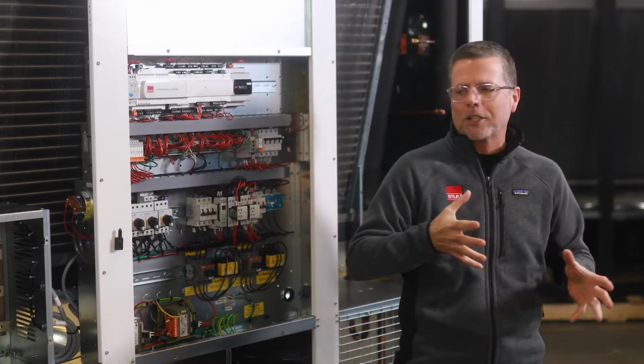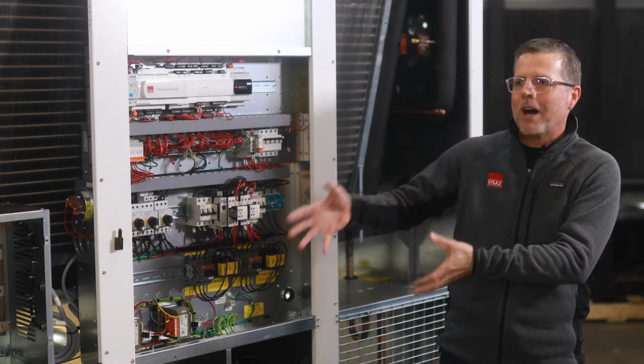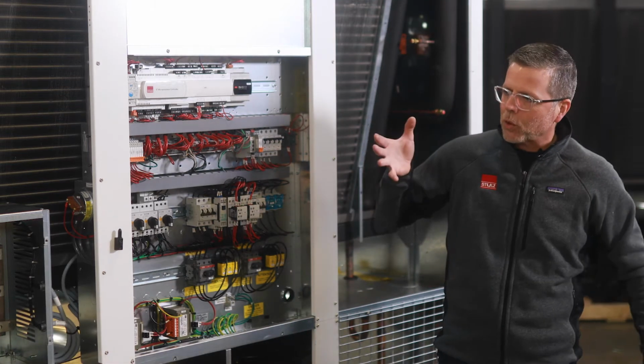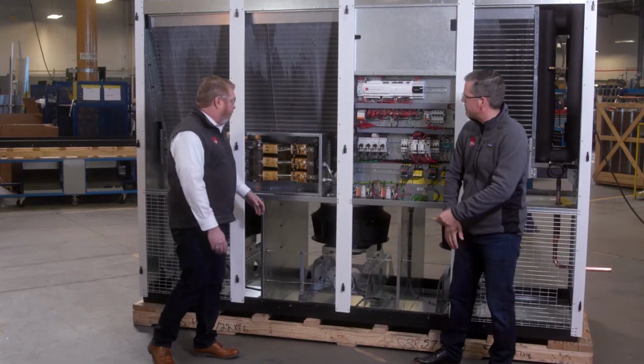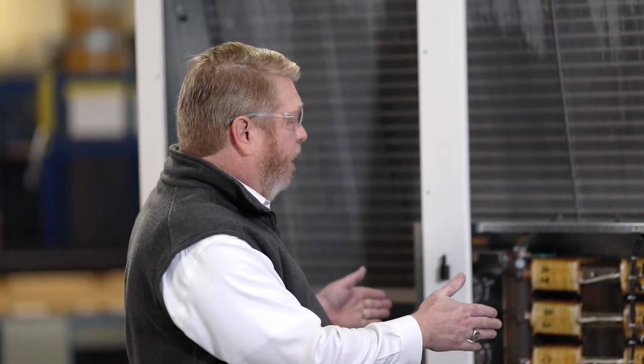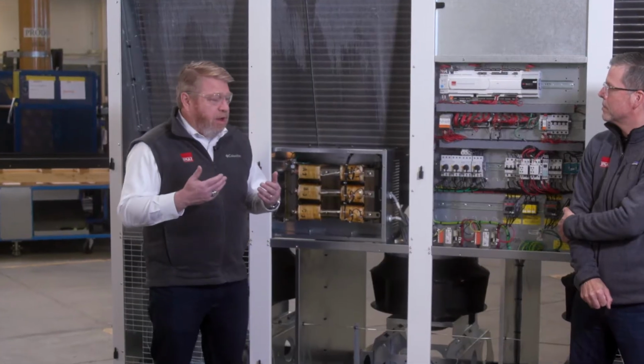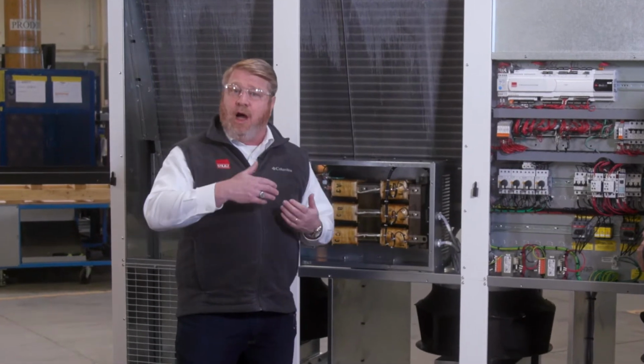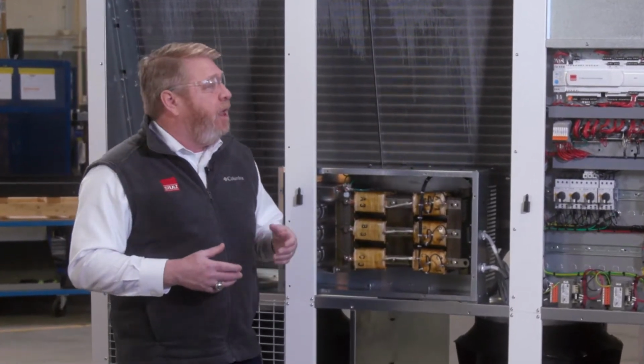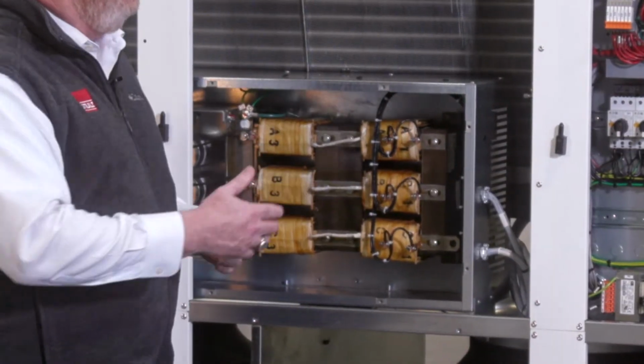So one of the special options that's configured, we've got harmonic mitigation in this box. Dave, do you want to dig in a little bit on harmonic mitigation? Yeah, absolutely. Fortunately, we have this harmonic mitigation in this unit so we can talk about it. If you're not familiar, if you have a sinusoidal input signal coming into the unit and you have multiple variable speed or variable frequency devices, a lot of times additional information is added to those signals at different harmonics, which can be very detrimental to the equipment downstream in the electrical distribution system.